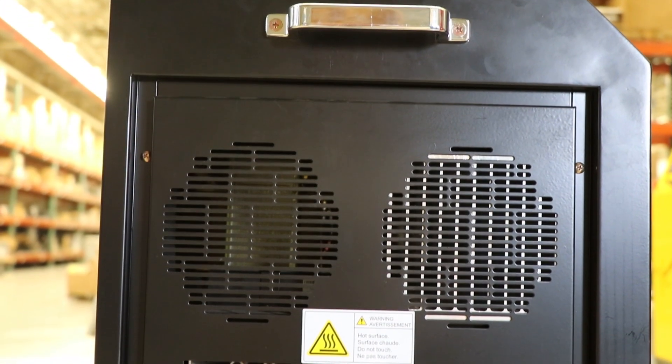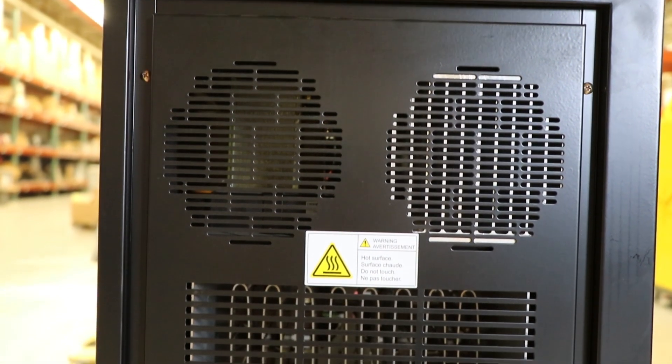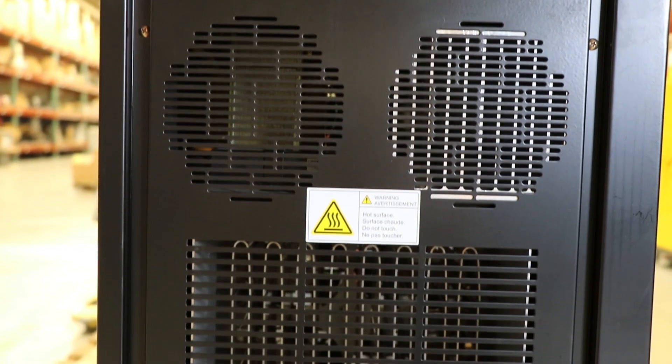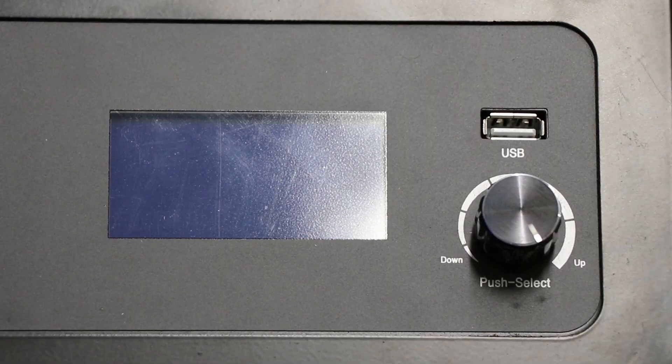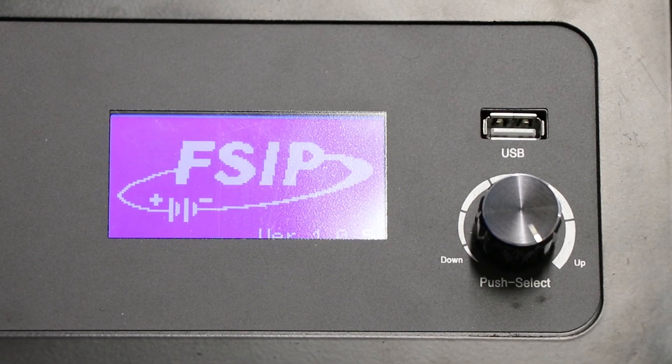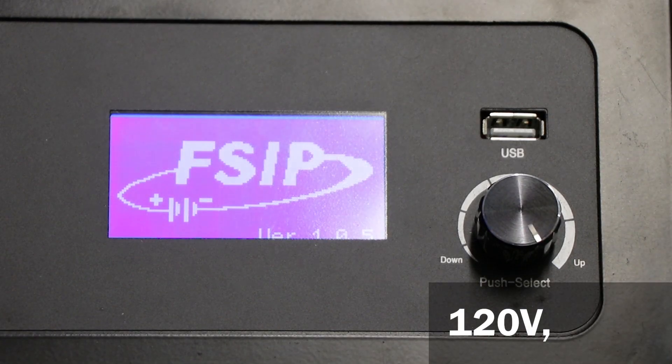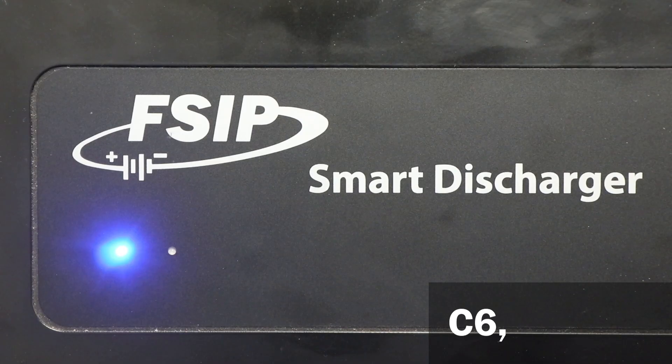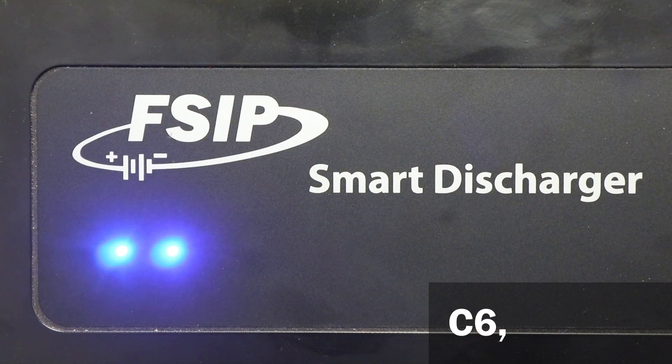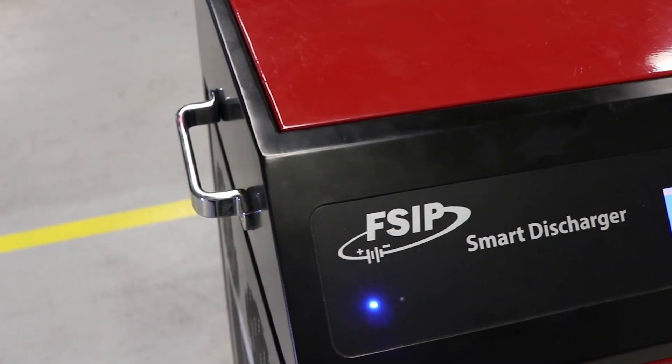Discharging is an important part of testing the health of a battery to determine how it will perform. The Smart Discharger uses a 120 volt AC input to discharge at a constant current of up to 200 amps, allowing a C6 discharge rate on 1200 amp hour batteries.